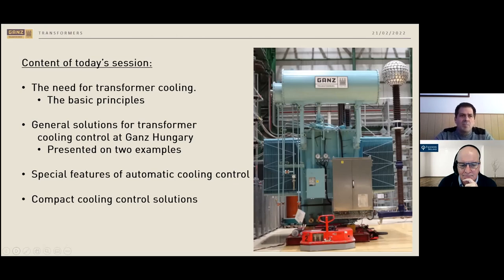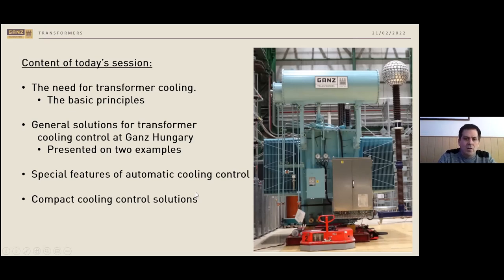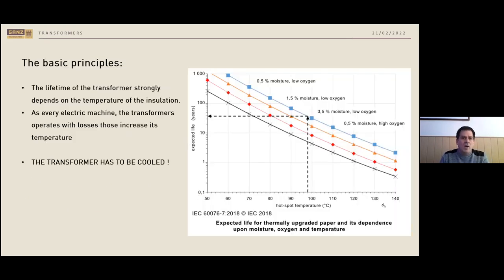The duration of my presentation is planned to be about 40 minutes, and in the last 20 minutes I will try to answer your questions. Whatever cannot be answered today will be answered offline by email in the following days. So why is cooling needed for transformers? On this slide you can see a graph where the expected lifetime is shown versus the operating temperature — the highest temperature spot of the winding. If the winding temperature increases by 10 degrees, the transformer lifetime drops to half.